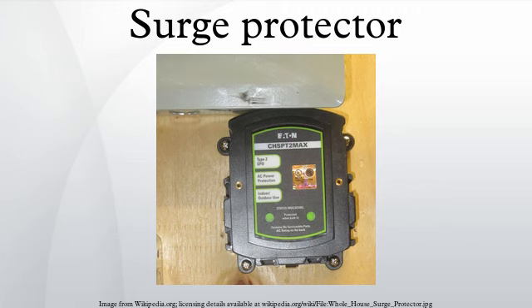All MOVs have response times measured in nanoseconds, while test waveforms usually used to design and calibrate surge protectors are all based on modeled waveforms of surges measured in microseconds. As a result, MOV-based protectors have no trouble producing impressive response time specs. Slower responding technologies may have difficulty protecting against fast spikes. Therefore, good designs incorporating slower but otherwise useful technologies usually combine them with faster-acting components, to provide more comprehensive protection.